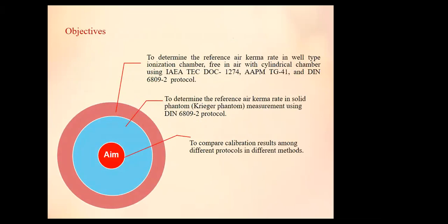So, what are the objectives of this study? To determine the reference air kerma rate in a well-type ionization chamber and free in air with a cylindrical chamber, using the IAEA TECDOC 1274, AAPM TG-43, and DIN 6809-2 protocols. Also to determine the reference air kerma rate in a solid phantom, also known as the Krieger phantom measurement, using the DIN 6809-2 protocol. And finally, to compare calibration results among different protocols and different methods.